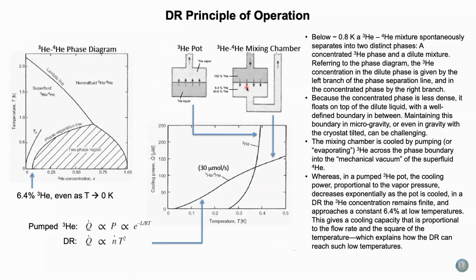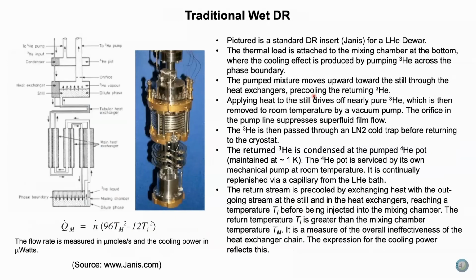But the nice thing about a dilution refrigerator is that the concentration of helium-3 in this dilute phase never goes to zero. And that gives a very different temperature profile. It gives a profile that's proportional to the square of the temperature, not through this whole range, but down, starting around 100 millikelvins. It's proportional to T squared, and it's proportional to the flow rate. So mixing chamber, like I said, is where the cooling takes place.